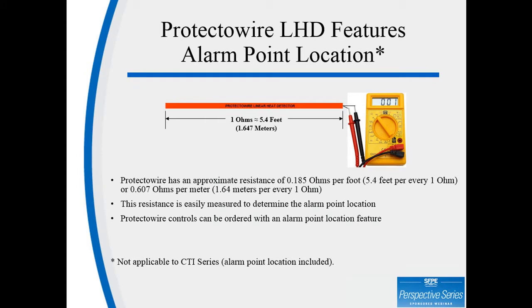One of the more important features of digital LHD is that we have the ability to pinpoint the exact location of the fire or overheat condition. This is called alarm point location. And due to the high resistance of the conductors, we can accurately measure the resistance from the starting point to where the fire is. As you can see on the line, Protectowire has an approximate resistance of 0.185 ohms per foot, 5.4 feet for every ohm, or 0.607 ohms per meter, or 1.64 meters per every ohm. This resistance is easily measured to determine the alarm point location.